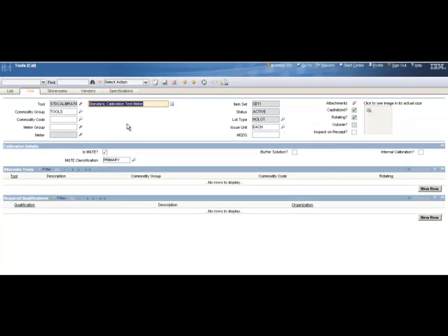The tool record basically has a tool ID. This standard value up here is a tool ID. This is actually located in the inventory table or the item master table. It basically has a different type of item, called, instead of an item like an inventory, it has a type called tool. What this does, these really are your calibration standards. It's the only time I really see these used for calibration standards. And a couple things you'll always find is the tool ID used for calibration standards will have it checked as rotating, and you'll have this button checked over here for is MTE, is measuring test equipment, and have an MTE classification, in this case primary standard.